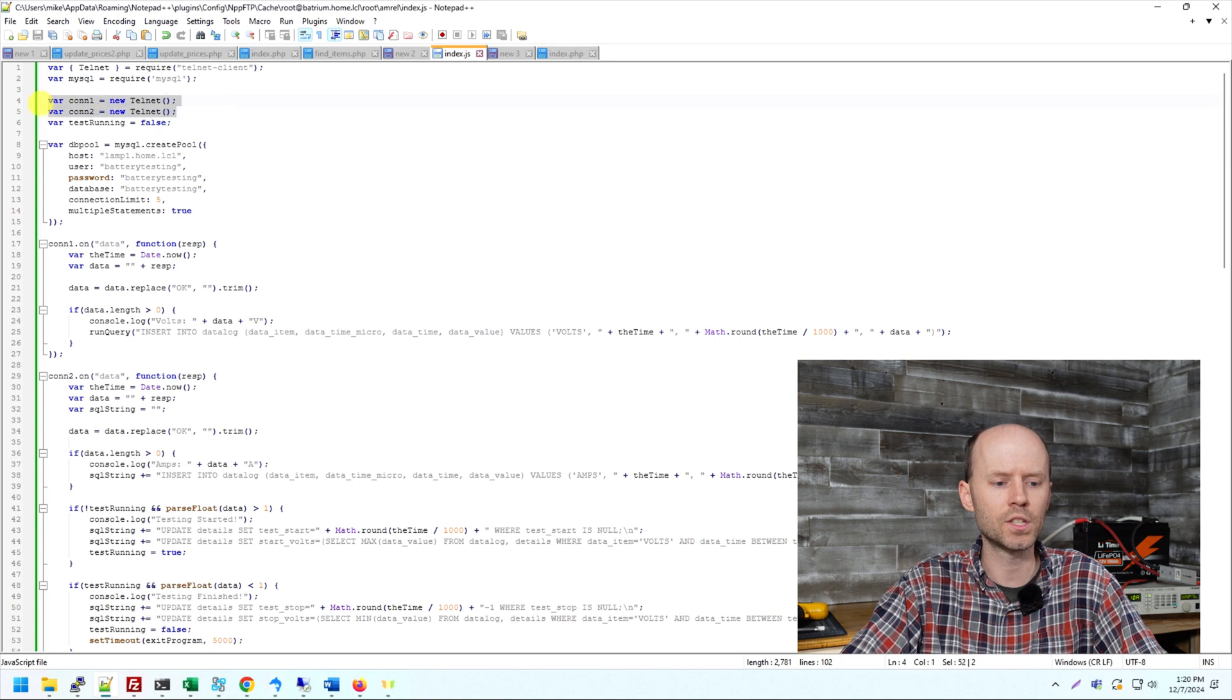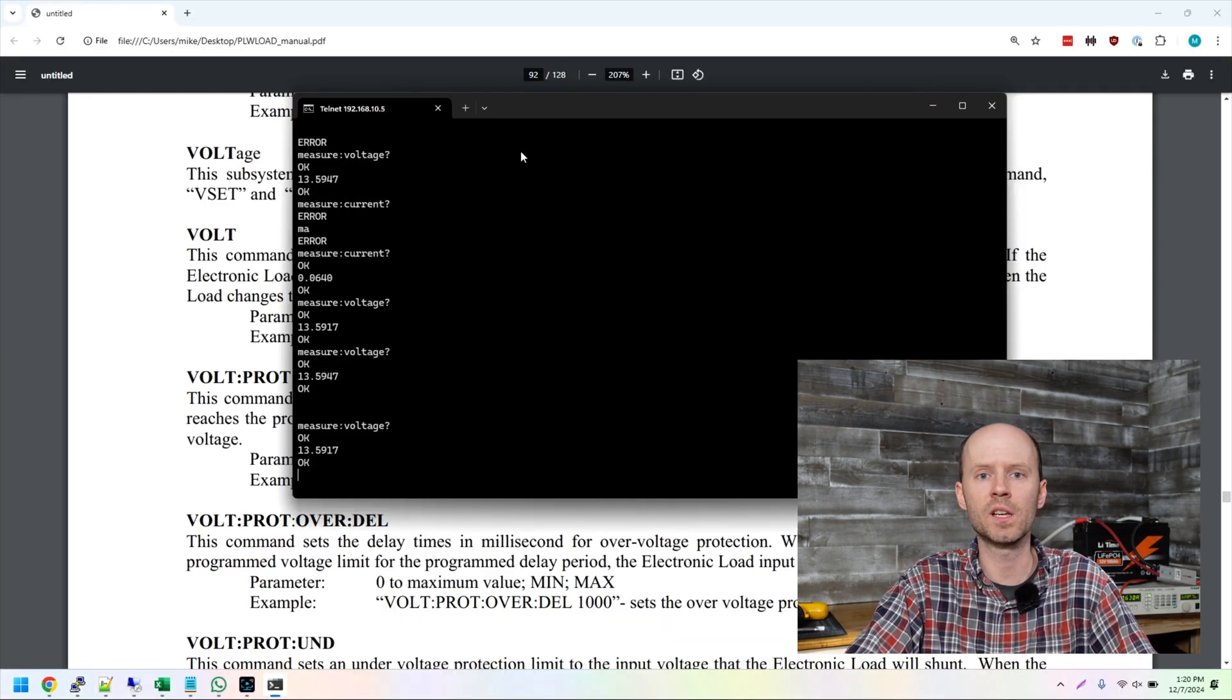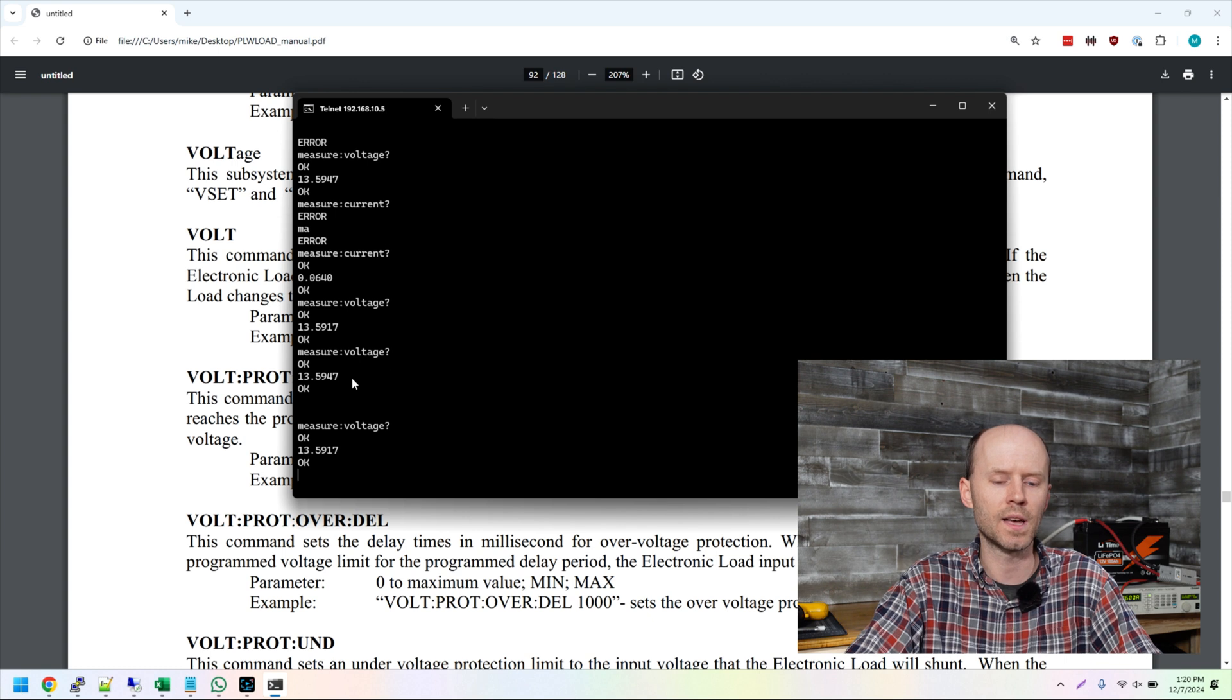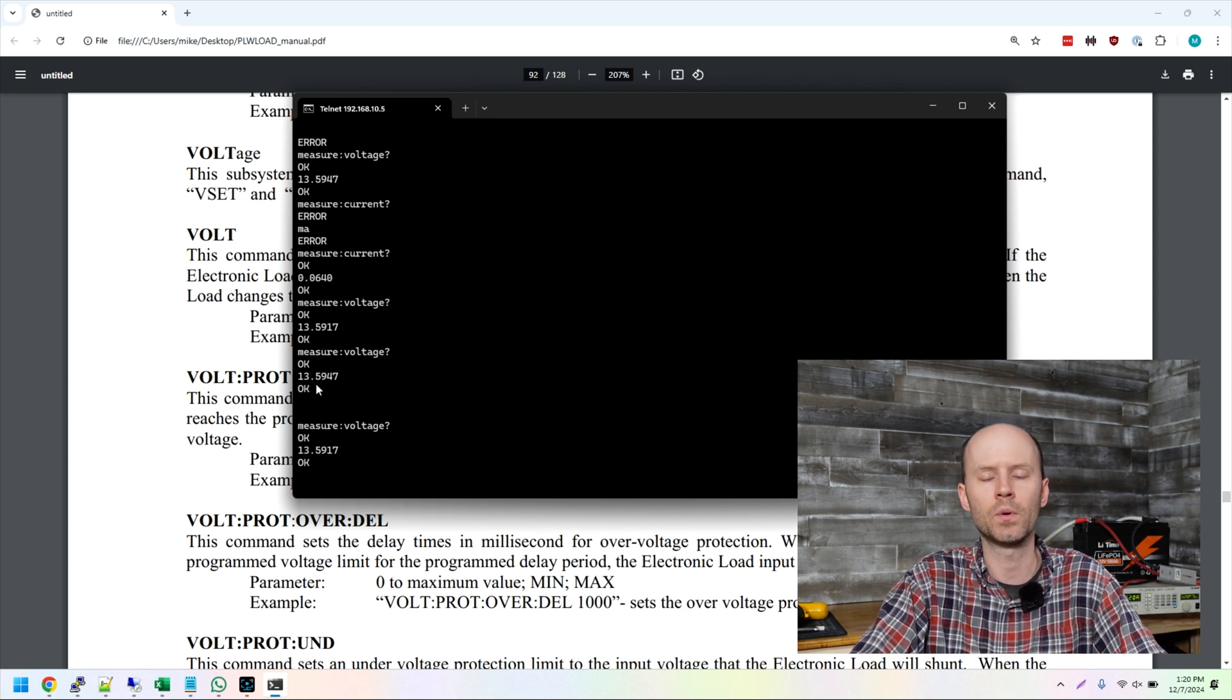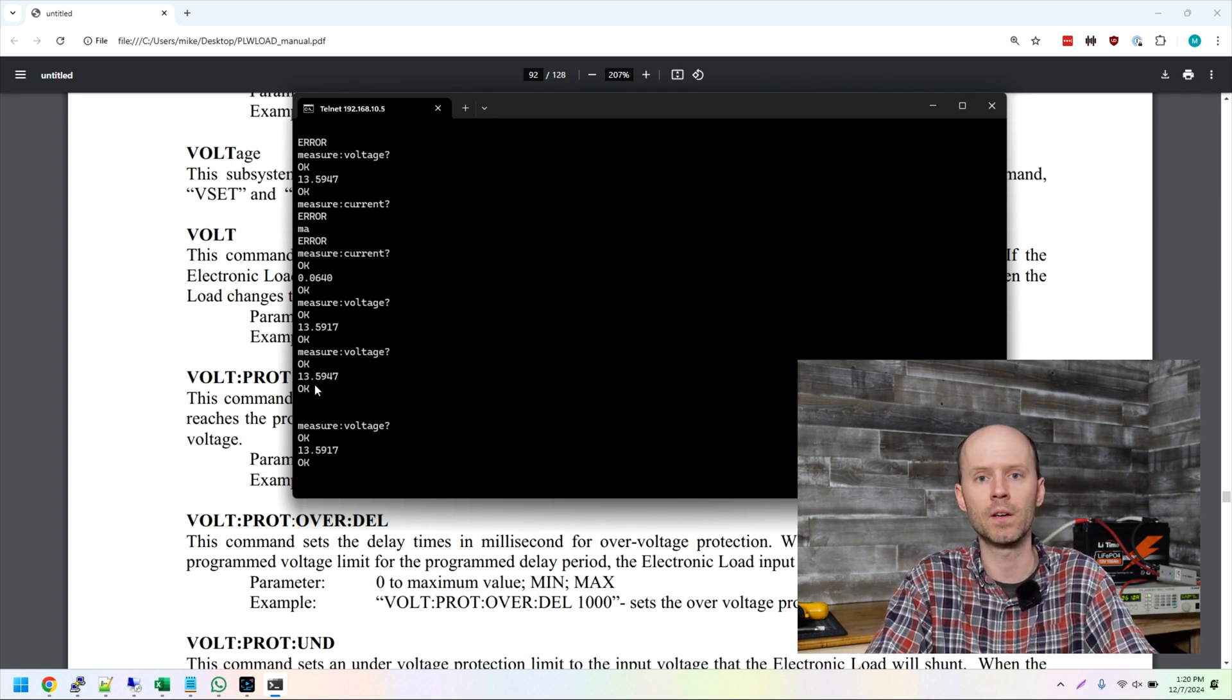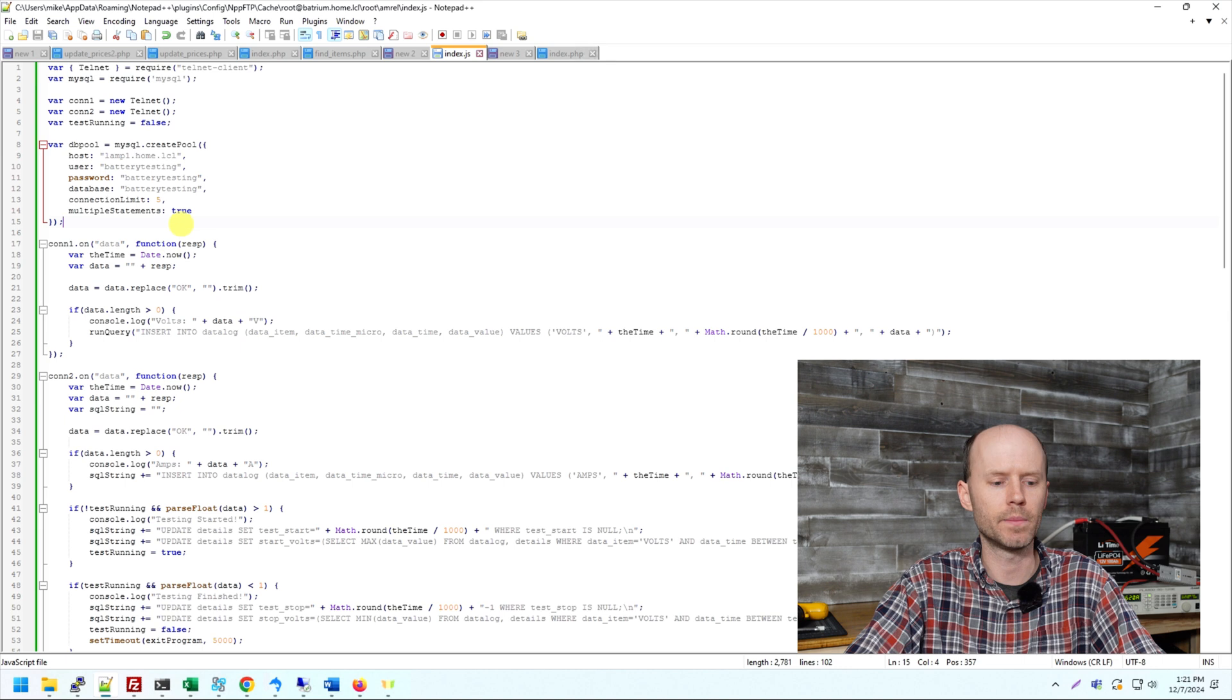So basically, I'm initiating two telnet connections. One connection is going to be used for the voltage measuring, and one's going to be used for the current measuring. And the reason why I'm doing it that way, because again, this is asynchronous. So I could send a measure voltage and a measure current over the same connection at the same time, because it's not waiting for a response. But the reason why I'm doing two connections is because, as you can see in this example, when you do measure current, it returns a decimal. When you run measure voltage, it returns a decimal. It doesn't give you a unit for this response. So you don't know if this 13.59 coming back is an answer to the voltage query or the amperage query, right? So by keeping the query separate in two separate telnet sessions, we know that in session one, it's always going to be the voltage, and in session two, it's always going to be the amperage coming back.